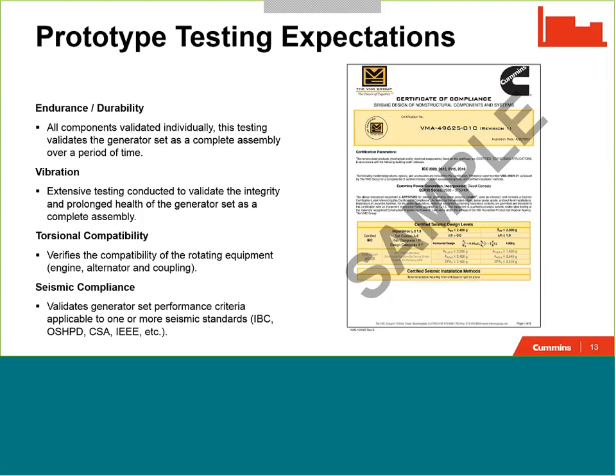Torsional compatibility is another key piece here. And what we're talking about with torsional compatibility is really the compatibility of all the rotating equipment: the engine, alternator, the coupling, and the radiator fan in particular. These are key because, again, a lot of the time these components are verified or validated by their individual manufacturer, but they may not necessarily have been tested together. This is the difference, key takeaway here. This is the big difference between a generator set assembler and a generator set manufacturer.